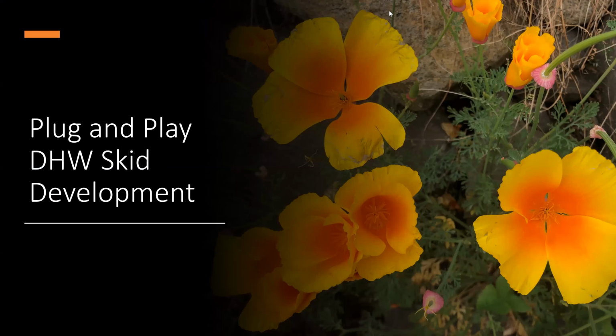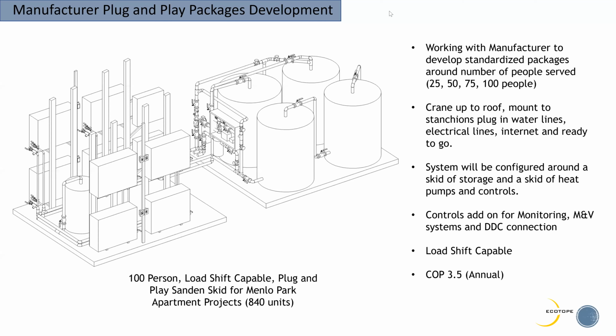I want to talk to you about some of the other tasks that are happening inside of the Advanced Water Heating Initiative. There's been a desire to develop plug-and-play domestic hot water systems. This is an example of a system that we're working on with the manufacturer. This would essentially be a rooftop skid-mounted approach. We've got a skid of heat pumps on the left, and a skid of storage tanks. The idea here is that we could plug in heat pumps from any number of manufacturers into storage tank skids.